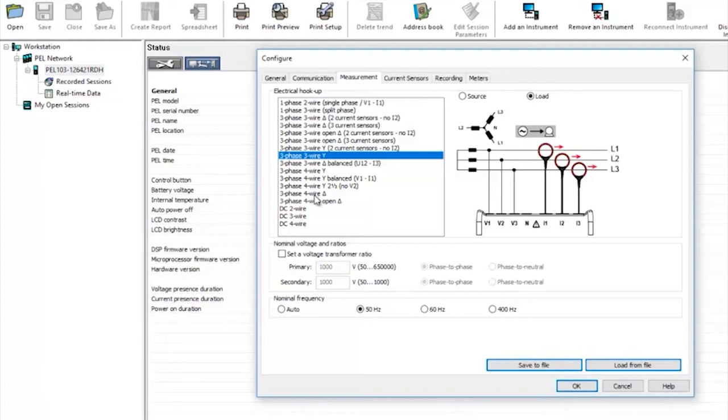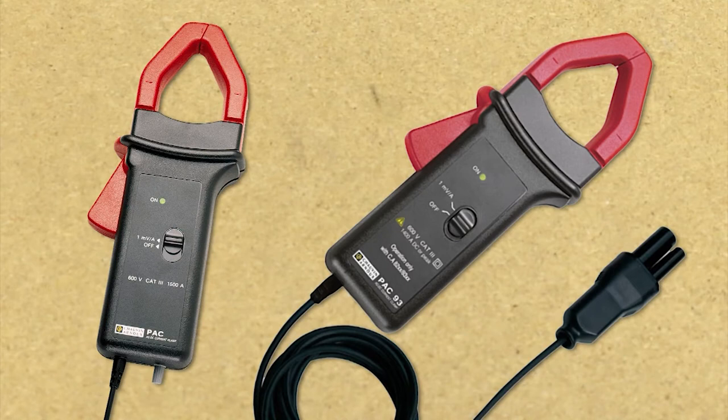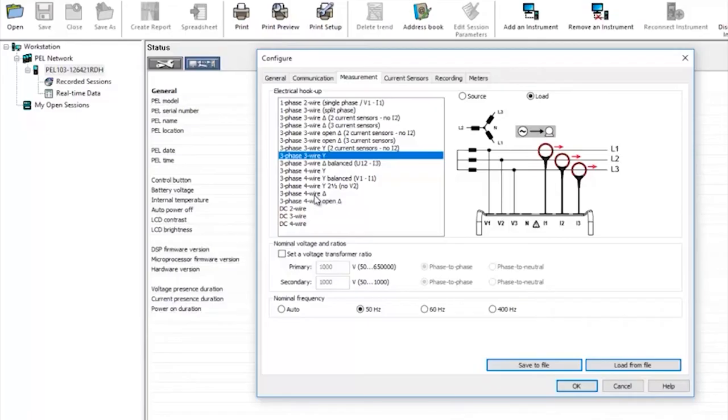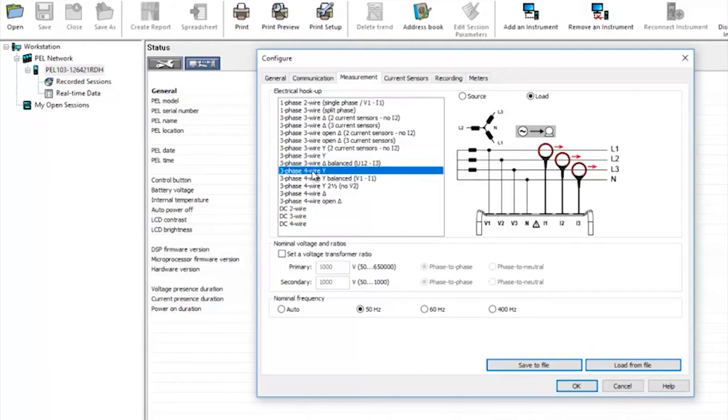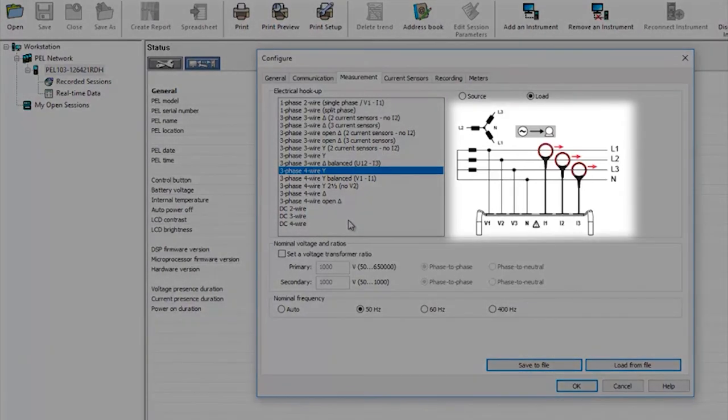If you're connecting to a DC installation you will need special DC clamps rather than the flexi clamps that come with the PEL as standard. For this demonstration I'll choose a three phase four wire installation and you can see from the diagram exactly how to connect the PEL to the installation.